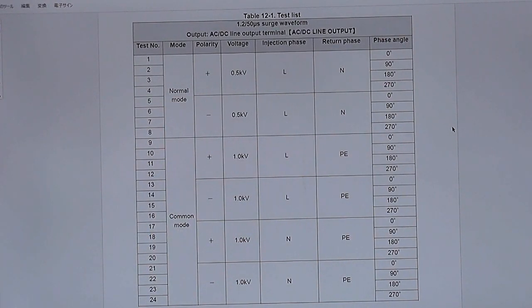And this table shows the conditions automatically generated by the system from what we've just set. So here we have normal mode and common mode, from plus polarity to negative polarity. For the normal mode 0.5 kV, common mode 1 kV, line to neutral, line to PE, and neutral to PE. Start phase angle from 0 degrees, followed by 90 degrees, 180 degrees, and 270 degrees. And the system will automatically run the test based on these conditions.